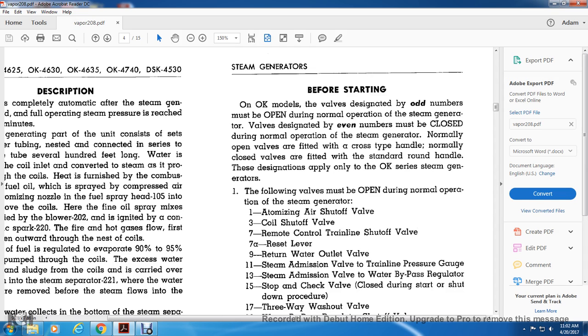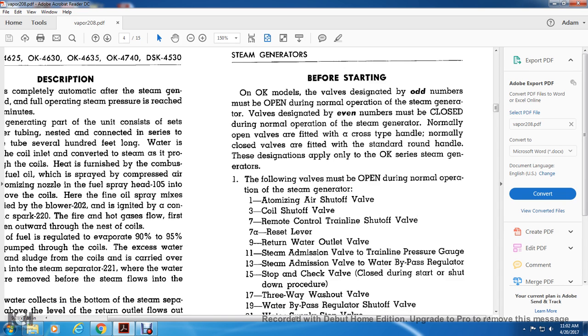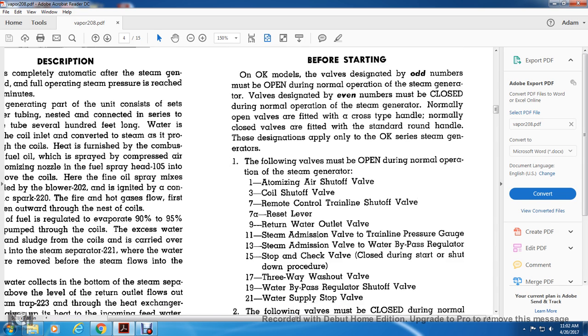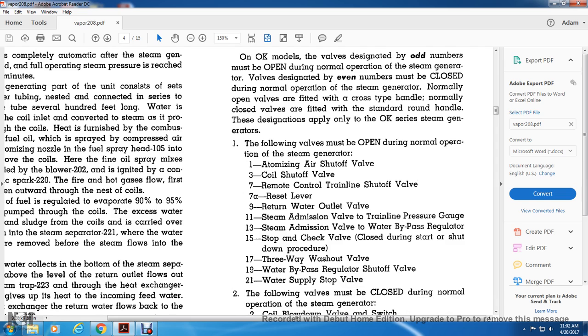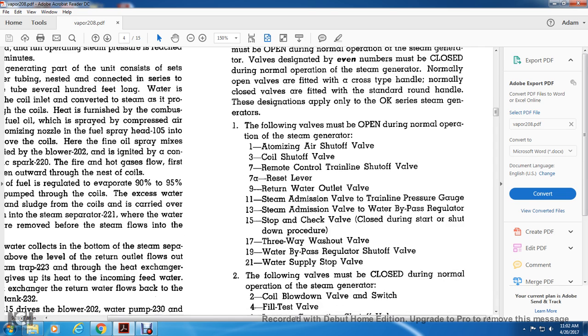The following valves must be opened during normal operation of the steam generator. 1, the atomizing air shutoff valve. 3, the coil shutoff valve. 7, the remote control train line shutoff valve. 7A, the reset lever. 9, the return water outlet valve. 11, the steam admission valve of the train line pressure gauge. 13, the steam admission valve of the water bypass regulator. 15, the stop and check valve, closed during the start and shutdown procedures. 17, the three-way washout valve. 19, the water bypass regulator shutoff valve. 21, the water supply stop.